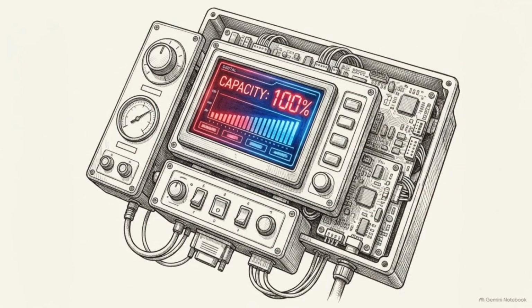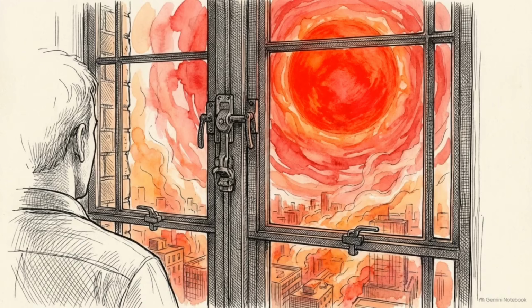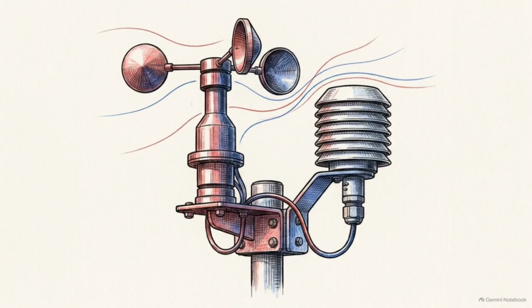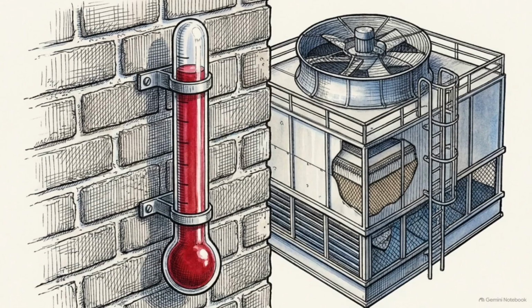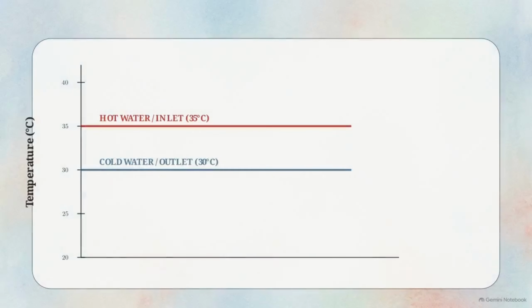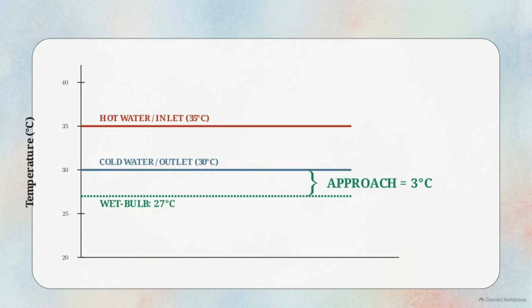It shows exactly what the tower did, but it reveals nothing about how efficiently the tower is capable of operating. To determine efficiency, we have to look outward and measure the environmental constraint. Standard dry bulb air temperature is mechanically irrelevant here because it does not account for atmospheric humidity. Instead, we use the wet bulb temperature, which represents the air's absolute evaporation potential. Let's plot our ambient wet bulb at 27 degrees. The delta between the cold water leaving the tower and this ambient wet bulb temperature is called the approach. Here, we have an approach of 3 degrees.